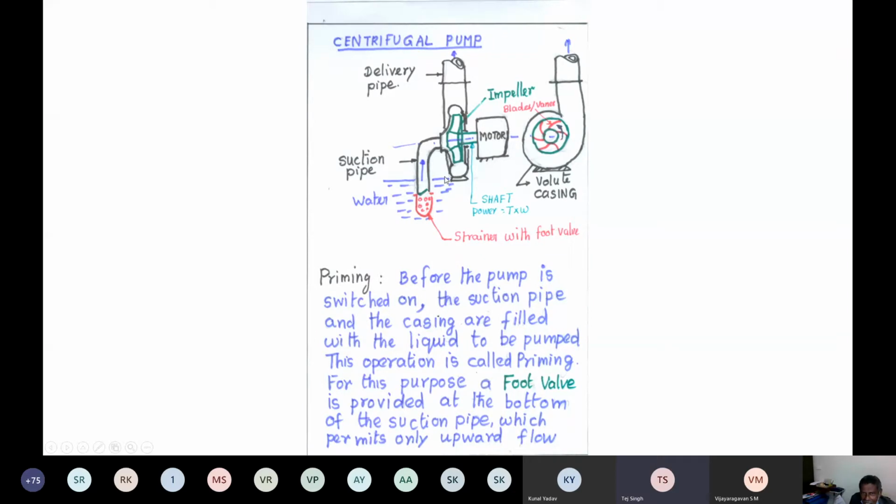Why? Because at the start, if there is air, air is compressible and the pump goes into compressing the air rather than creating the pressure difference. Whereas liquids are incompressible and then the liquid is pumped up. You are all trying to give reasons, but maybe intuitively you feel that it will not work, isn't it? You would have experienced it somewhere, or heard it somewhere, and you feel that it will not work.